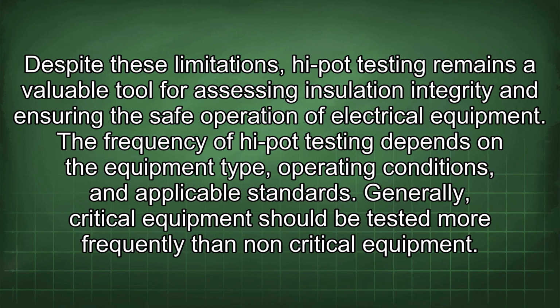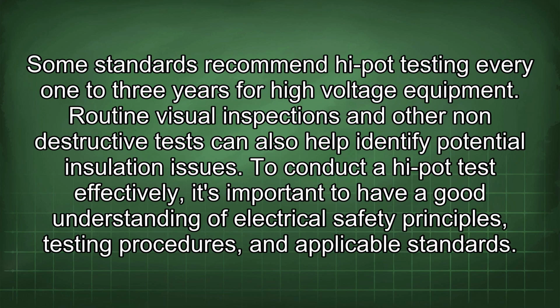The frequency of hi-pot testing depends on the equipment type, operating conditions, and applicable standards. Generally, critical equipment should be tested more frequently than non-critical equipment. Some standards recommend hi-pot testing every 1 to 3 years for high voltage equipment. Routine visual inspections and other non-destructive tests can also help identify potential insulation issues.